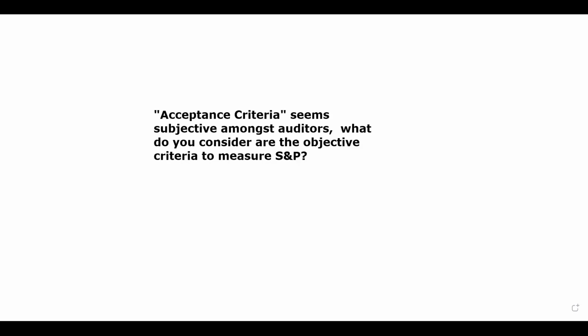And then, so for safety, you need to be no higher than the top range for any safety objective. Your device should perform at least as well or better than the top number from your competitors. Whereas for performance, it's the opposite, as Sarah said. You should be at least as good as the least performing of your competitors. So that's the bottom range. We just wanted to make that very clear. That's what has been acceptable in the clinical evaluation in the MDR world. And we have no reason to think that it wouldn't be the same for IVD.